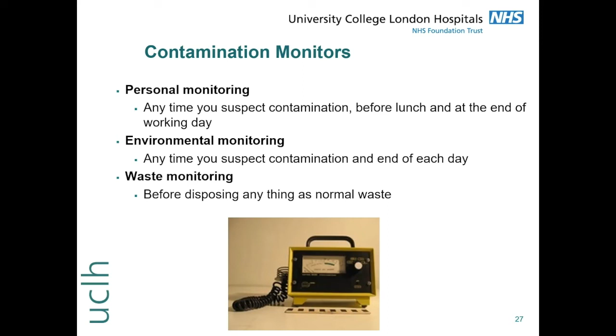The Ionizing Radiations Regulations 2017 regulate the exposure of staff and the public arising from work with ionizing radiation. Key aspects of these regulations include implementation of dose limits, requirements to perform risk assessments prior to starting any new or changed work, implementing the findings of these risk assessments where necessary into the local rules, and providing contingency plans in the event of unexpected occurrences. The employer is advised by the Radiation Protection Advisor on how to comply with IRR 17, and locally, compliance with the local rules is supervised by the Radiation Protection Supervisors.